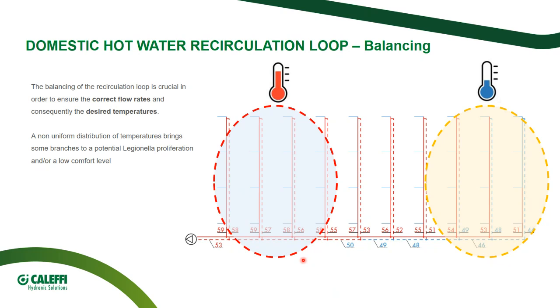So I can have a risk of scalding and danger. An area where the temperature is not enough, it's not what I designed, because it's a matter of system balancing. So in this orange area, I am not giving enough thermal power, and the result is poor comfort and possible Legionella proliferation. So I have to take this aspect into account in order to grant the safety throughout all the building. The area in between is more or less fine, but its condition of safety depend on the usage rate, on the demand, because if everybody is asking for hot water in another part of the building, this area will get colder too.